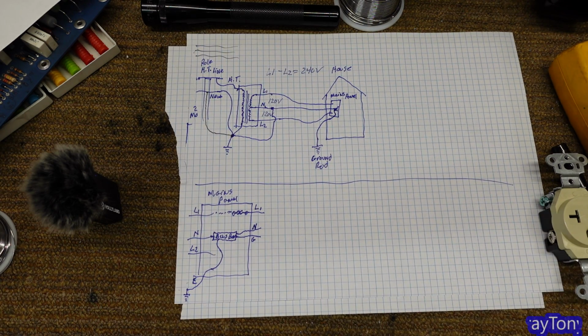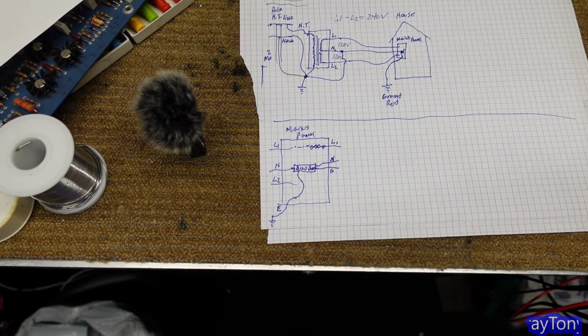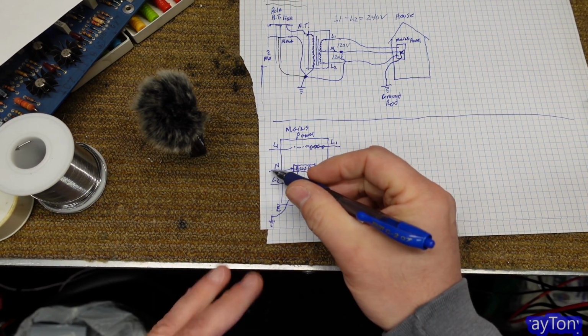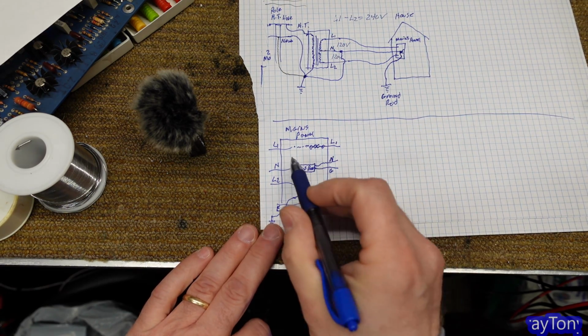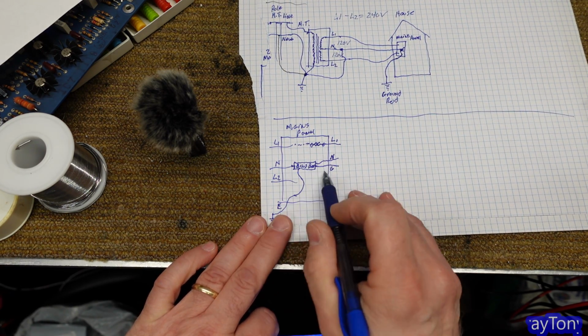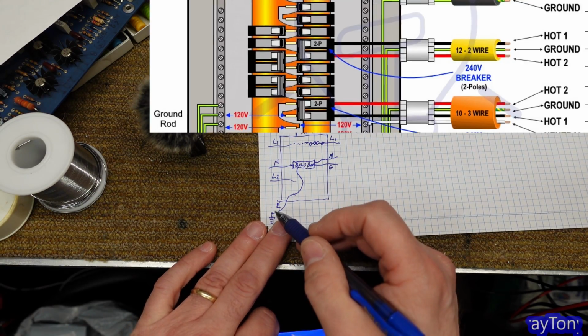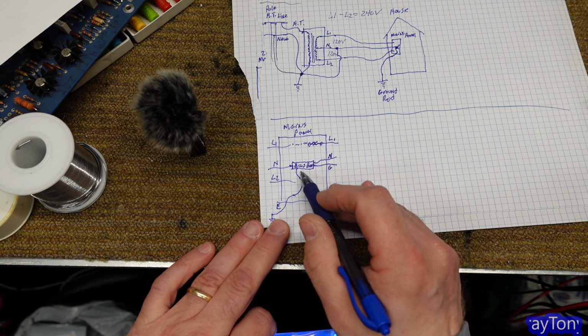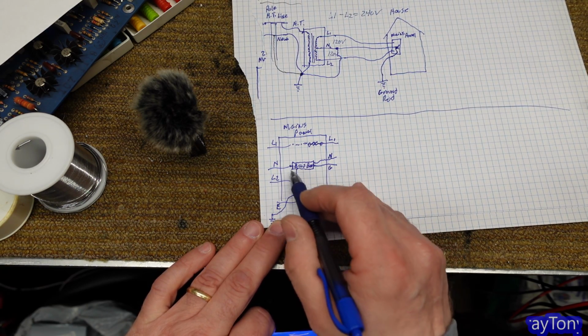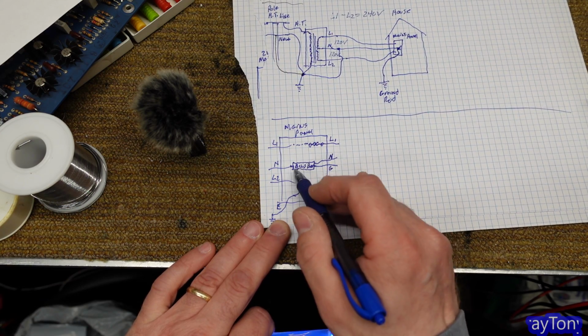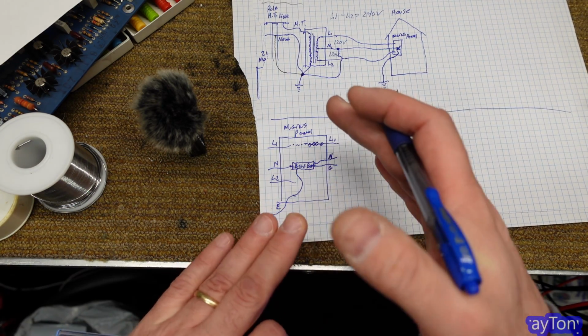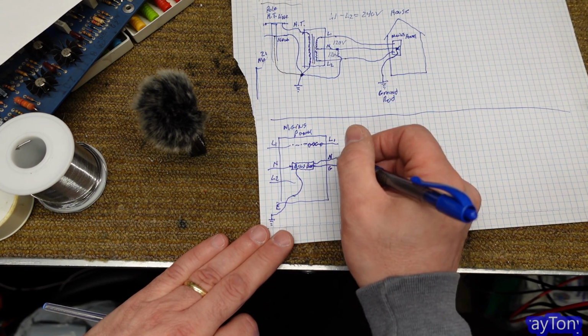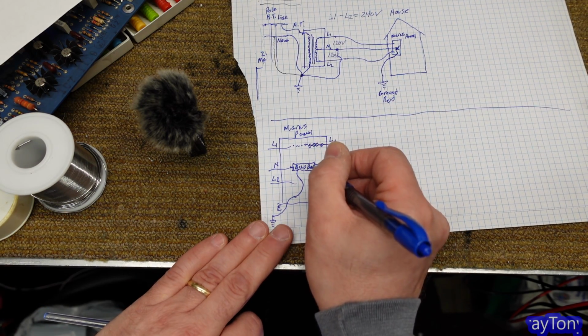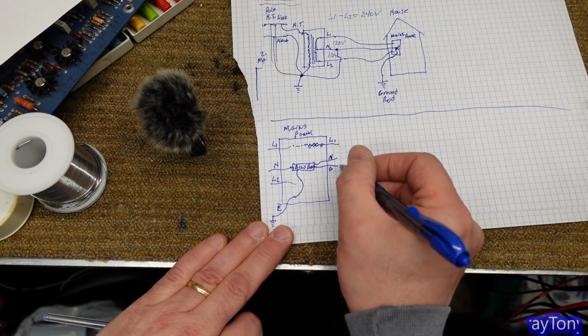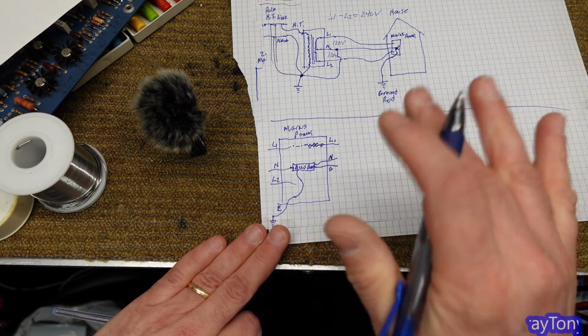Now, getting a little bit closer, if you look at your mains panel, inside there, you have your neutral coming in and your L1 and L2. In the case of the ground, you have a ground rod at your house. And that ground rod comes up and goes to a bonded bus bar. And the only place that the neutral and the ground will be bonded together, will be connected common to the same connection point, is your main entrance panel to the house. Anything that goes out of there, you'll have 2 wires connected to the same place, but they'll never touch each other again for the rest of your house, if it's done right.